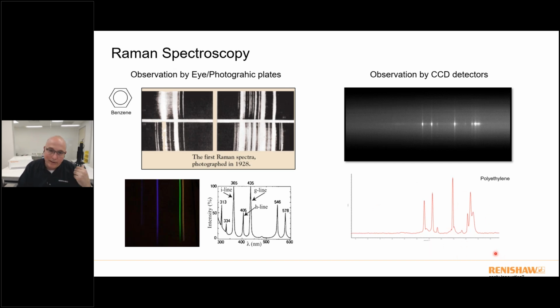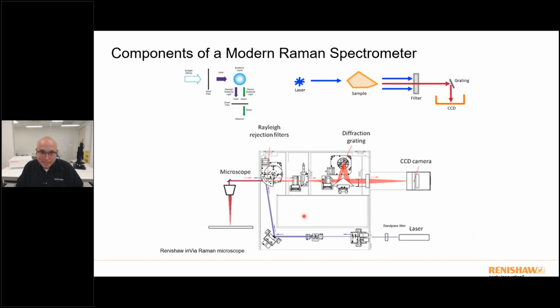So this is a spectrum of polyethylene I acquired just the other day. So it's all very interesting, and you can see maybe why I get a little bit passionate about Raman spectroscopy and the history here. But fundamentally, the instrument design here isn't significantly different than what Raman did. And so we always have a laser source, we illuminate some sort of sample, we look at the scattered light, we filter away the laser, and we only look at the photons that have changed in energy, and we disperse it onto our detector, which is a CCD.